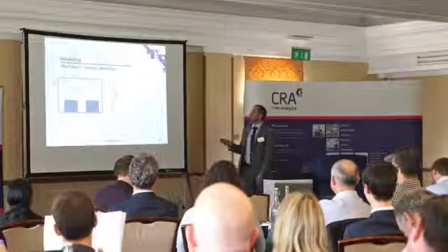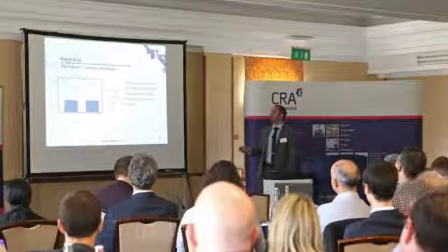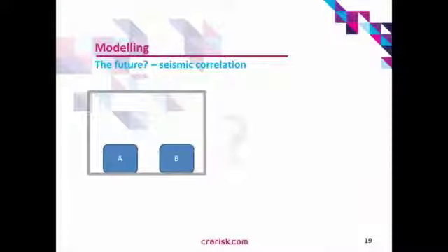The key thing is, could one fail and not the other one, do we think? Think so? They're both qualified. If you're not convinced, what if this wasn't seismic? What if this was temperature? Let's say that they're qualified to take up to 50 degrees Celsius, they operate at 25, and the room temperature sneaks up to a cheeky 40 on a very warm day. Would you assume they both fail? Straight out? No, too conservative. So why is it different for a seismic event when they're qualified?